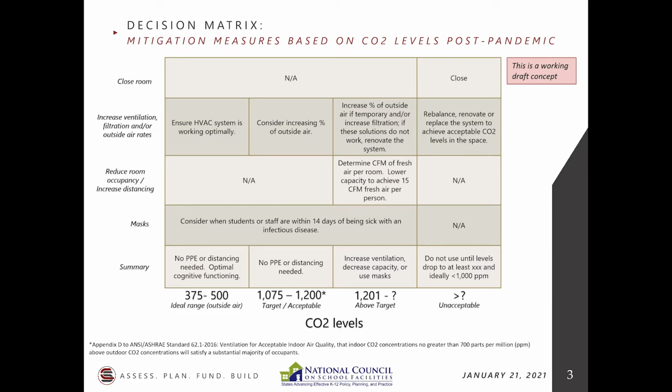Now, if you have, which often we do, multi-zone operation in a school, you have to understand that the empty classroom next door or down the row is going to influence the levels that you're recording in, say, the occupied classroom. So that's one of the assumptions that we often overlook and say, hey, things are fine. You might make the assumption that things are wonderful here, but in fact, what you're getting is the mixed air from the other classrooms where you don't have occupancy.